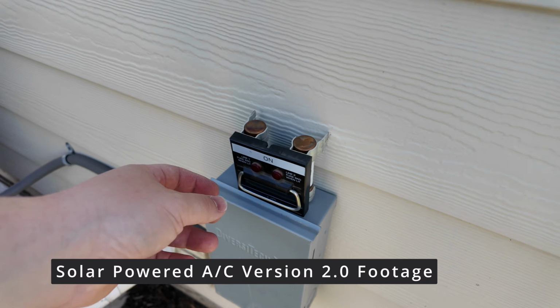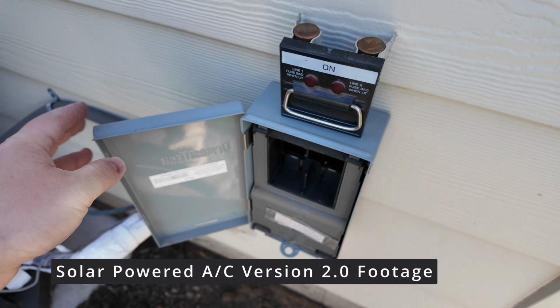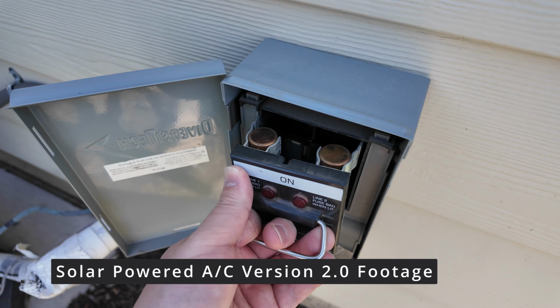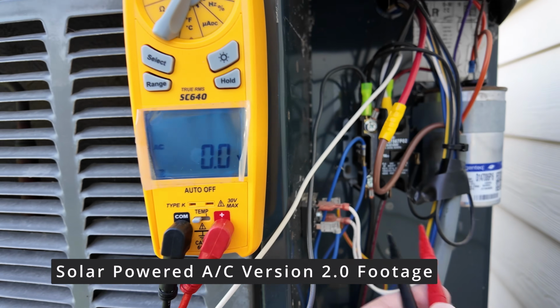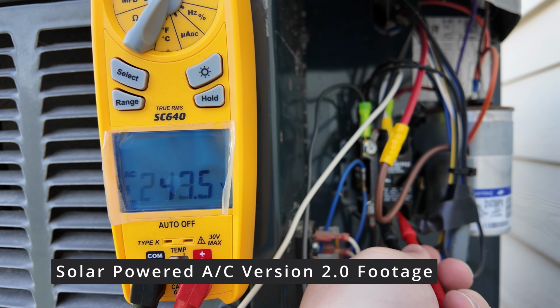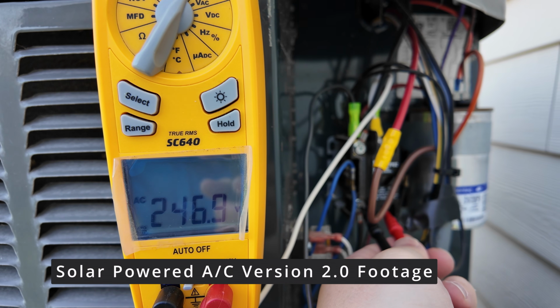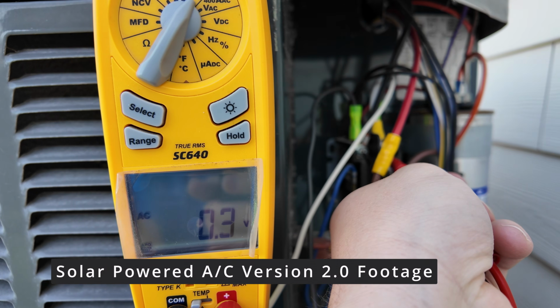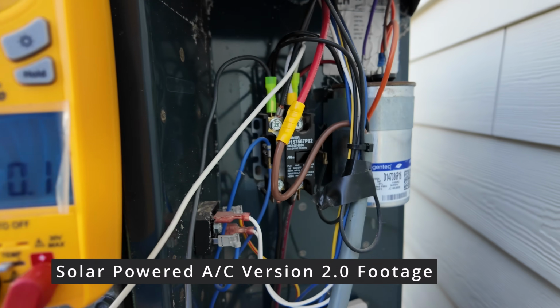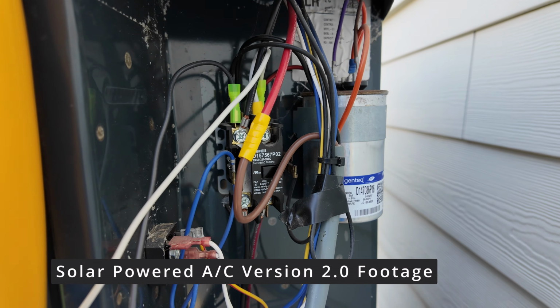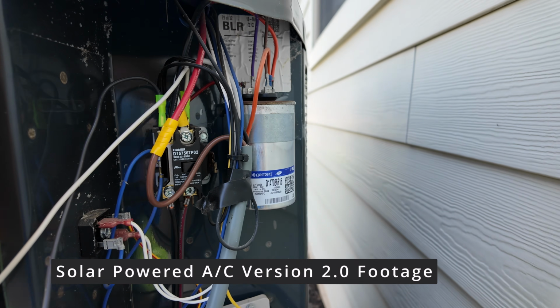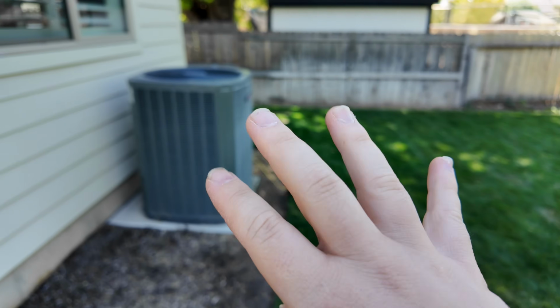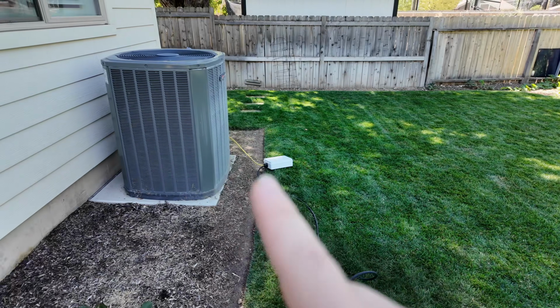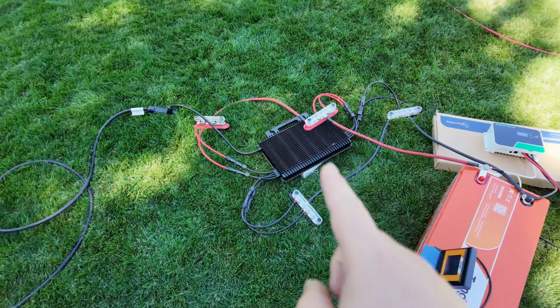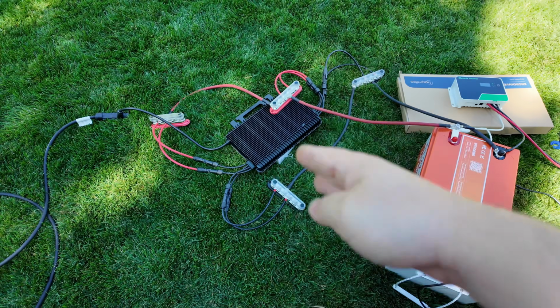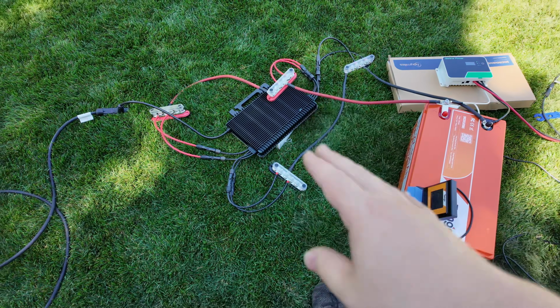Then we're going to come over here and we're going to go ahead and put the service disconnect back in over here. And now you'll see, waiting to come into the contactor at the bottom, we've got 246 volts, but up at the top we have no voltage because the contactor is still switched off. We've got to go in and turn it on from the thermostat. There is about a 4-ish minute delay from when that turns on and this microinverter starts seeing grid power before it starts producing power. That's a safety feature.